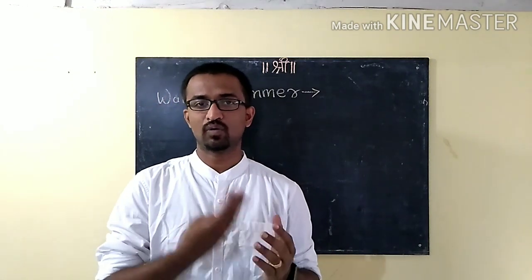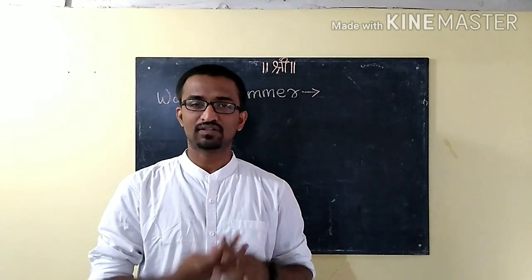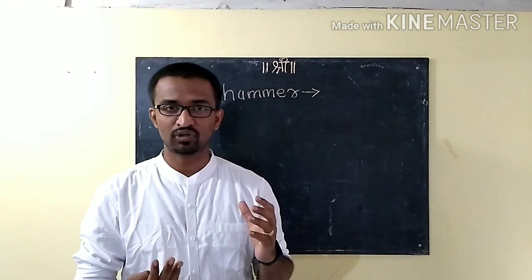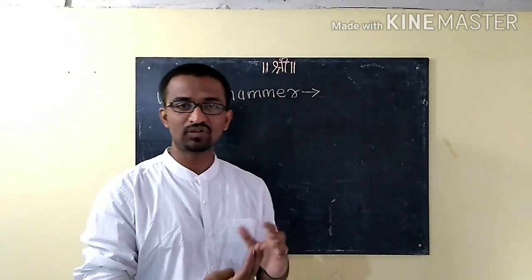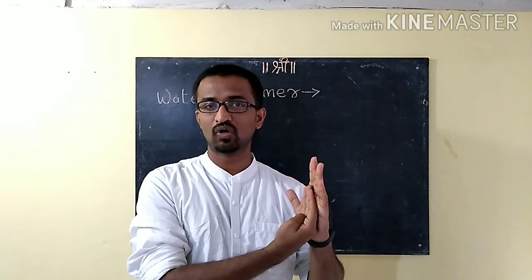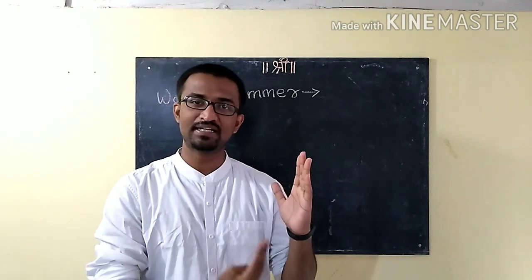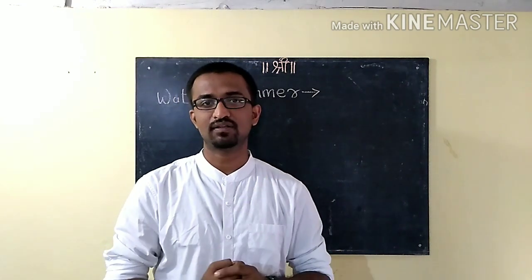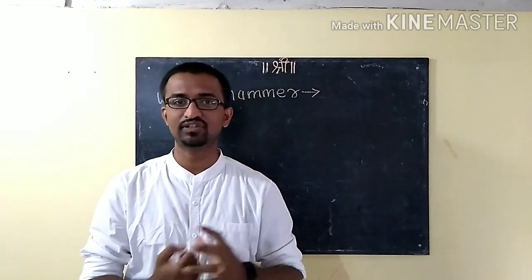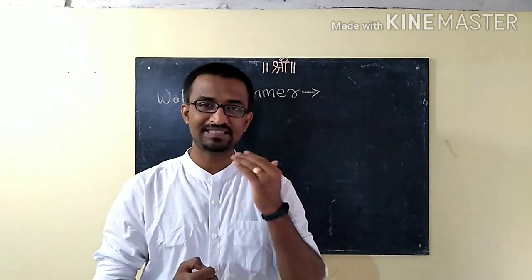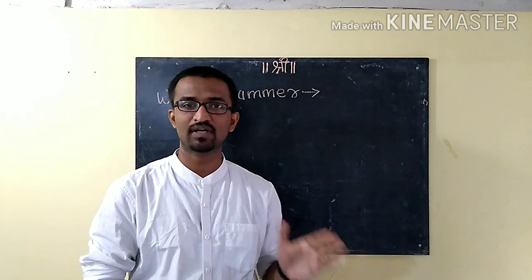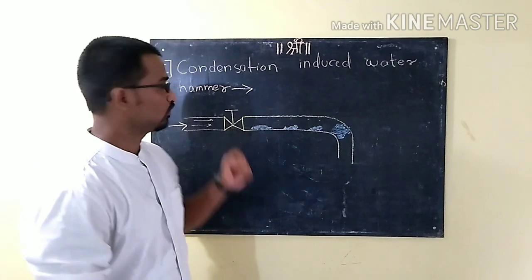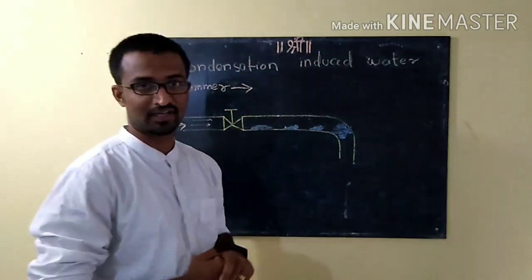During this phenomenon, the water gets kinetic energy. Sometimes its velocity is very high compared to a normal steam velocity, and this high velocity, high kinetic energy water goes and impacts on some bend or joint, and suddenly that kinetic energy gets converted into pressure energy, and pressure pulsation is generated, or you can say a banging noise is generated. So now we will discuss in detail the types of water hammer, why they occur, and then how to prevent water hammer.